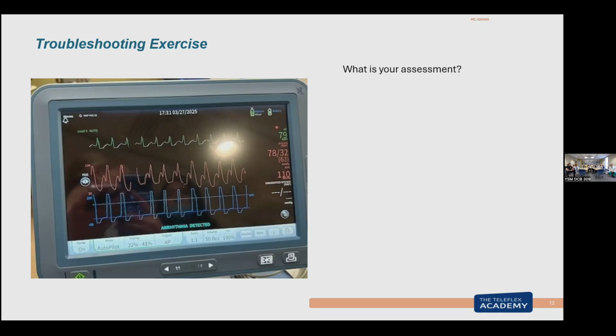So is that a yellow alarm or a blue banner? So that's a kinked line. What's the alarm you get on that? Right now, I'm not getting an alarm. This is getting back to baseline. It's not kinked enough that I'm getting a high pressure alarm or a helium loss. High pressure alarm means it's squaring out at 250. Still coming back to baseline. I'll show you those in a second. Helium loss is if it can't get back to baseline between the beats.